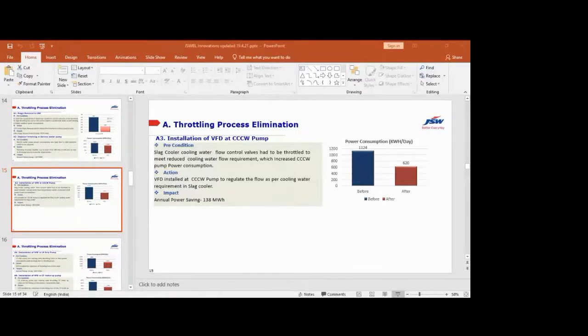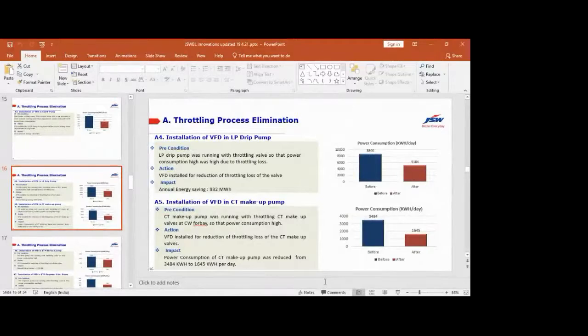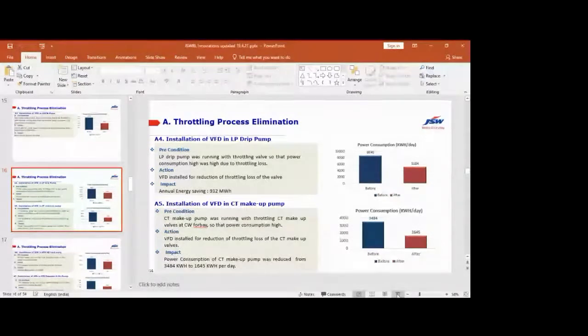Installation of VFD in the LP drip pump. The LP drip pump was running with a throttling valve, and that's why the power consumption was higher. We provided the VFD, and the impact is an annual energy saving of 932 megawatt hour.